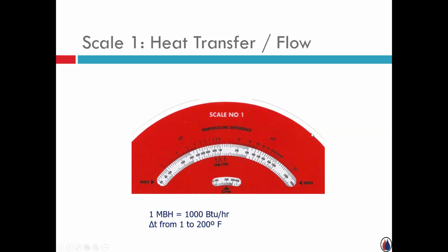And then above it is a scale. They reference it as temperature difference, or you might see it as the delta T, change in temperature, temperature drop or temperature rise, but a difference in temperature. So that's the details, if you will. And then this bottom little window here has the letters GPM with a pointer. So scale one works together. All it's talking about is BTU per hour, delta T, and calculating or finding out what the appropriate GPM would be for that set of conditions.